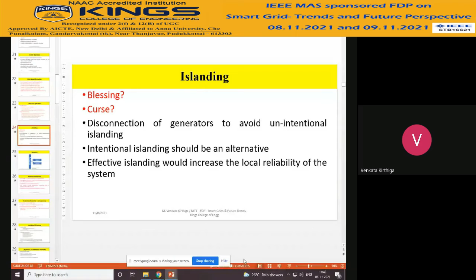Now coming to islanding - what exactly is islanding? Is it a blessing or a curse? When I call some event an islanding, I mean the disconnection of generators is called islanding. But it is not so simple. This disconnection of generators can happen with or without load, and it can happen as an accident, or intentionally to avoid unintentional islanding. If it happens without any intention, accidentally, we call it unintentional or accidental islanding.